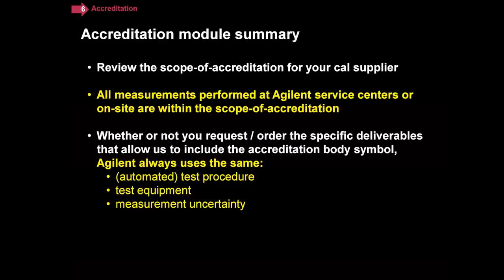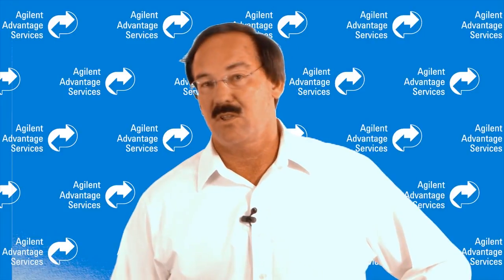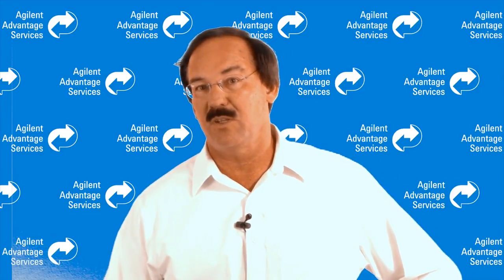I'd like to move to the closing points. Whenever you consider two laboratories, please review the scope of accreditation for the individual calibration suppliers — it's very important. We at Agilent feel it's so important that all the measurements we make are always within our scope of accreditation. And finally, whether or not you request the specific deliverables that allow us to include the accreditation body symbol, at Agilent we will always use the same automated test procedure, the same test equipment, and the same associated measurement uncertainty — so you'll always know that we're making accurate measurements, regardless of which of our services you select.